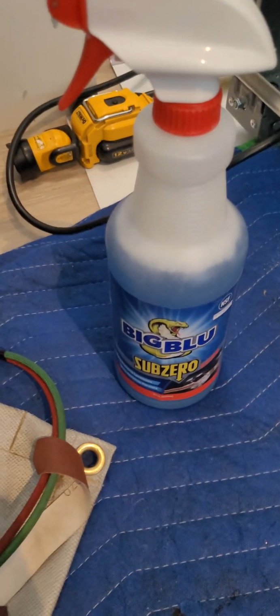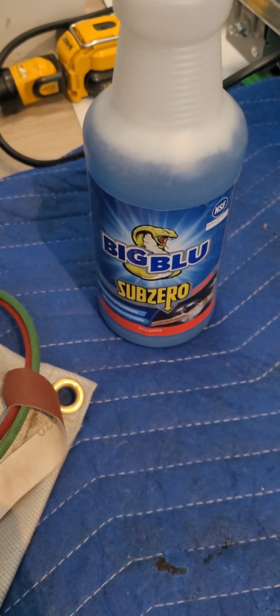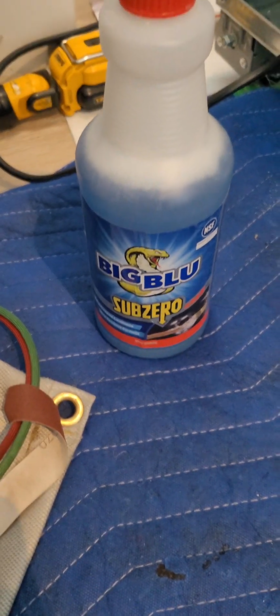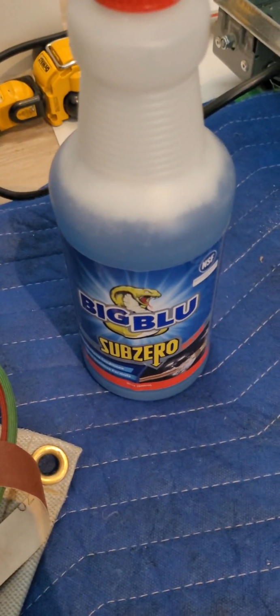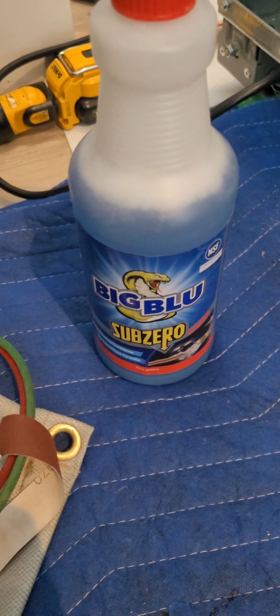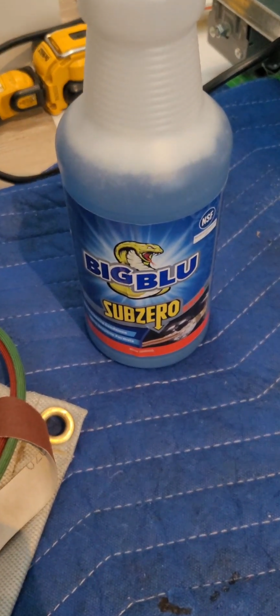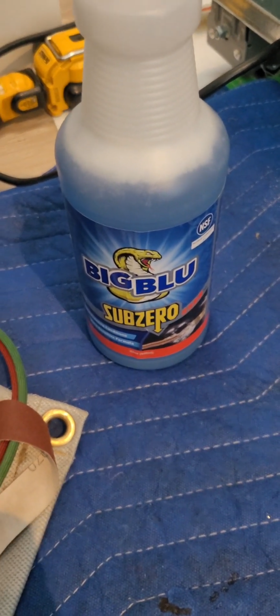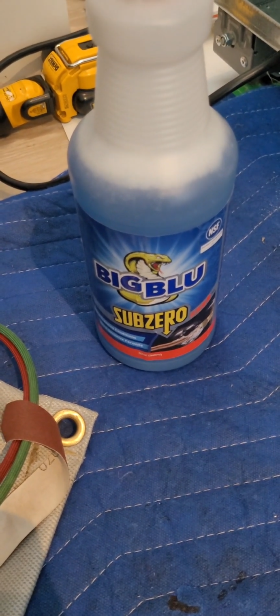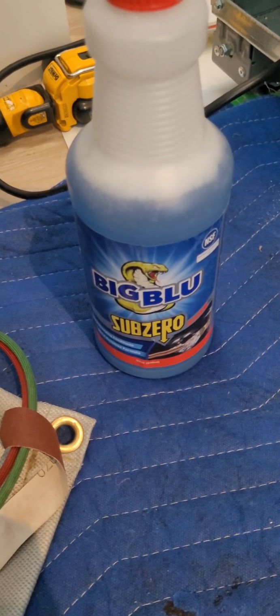So when I'm done doing my braze joints, I like to spray down my joints with some Big Blue Sub-Zero from Refrigeration Technology. It's awesome stuff. You can detect micro leaks, which is awesome. Some other bubble detectors won't produce any kind of micro bubbles, but this stuff works really well. So then I'll go through and check all my joints.